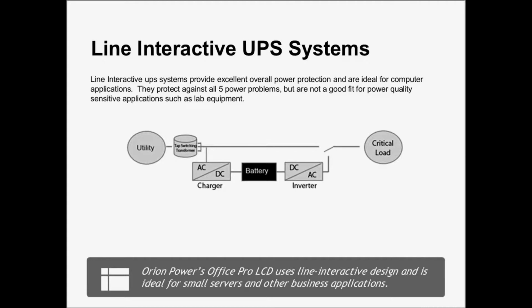The next one is a line interactive UPS. Essentially, what a line interactive UPS does is it's the same design as a standby, except it uses a tap switching transformer, and that regulates the voltage. So this unit again watches the power come through. The tap switching transformer tries to correct for it, but if it can't, then it throws the high-speed switch and runs off a battery, where it converts DC, which is battery power, into AC power, and then powers the load.